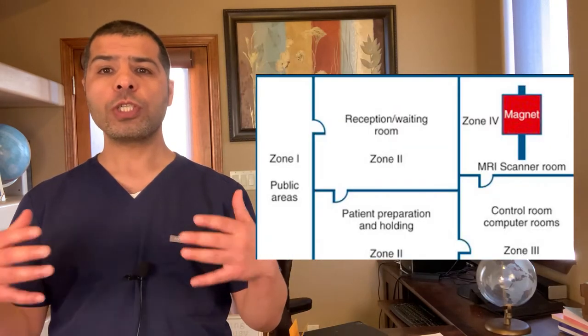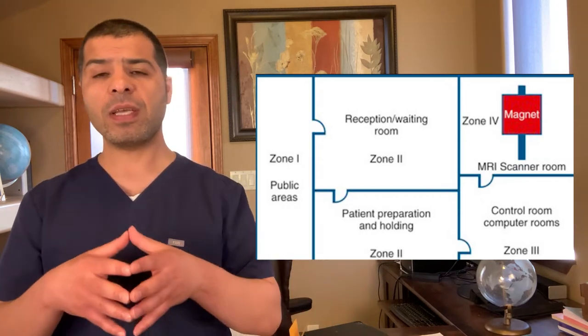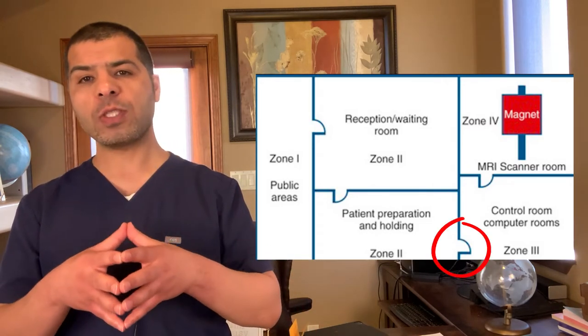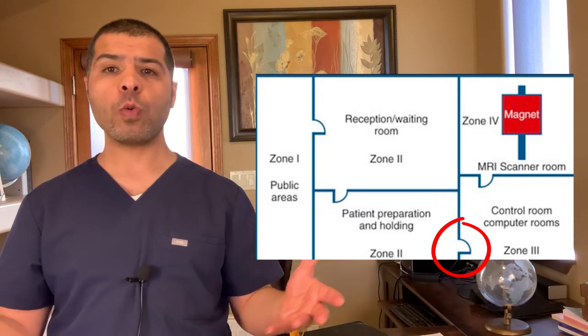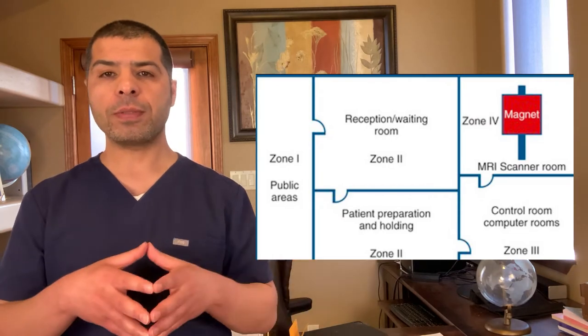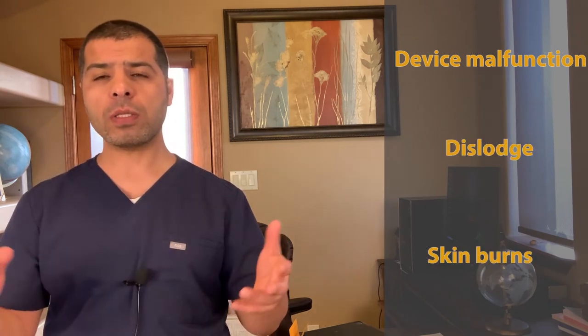Zone three is the area around the magnet room — there is a potential magnetic field in this zone, which is why there is usually a locked door between zone two and zone three. And finally, zone four is the magnet room itself, where the physical risks are at their greatest. Because of the strong magnetic field in zone four, it is very important to perform a thorough screening process to avoid any potential harm if any magnetic objects inside or outside the body are present. Device malfunction, dislodgement, and skin burns are all possible complications.